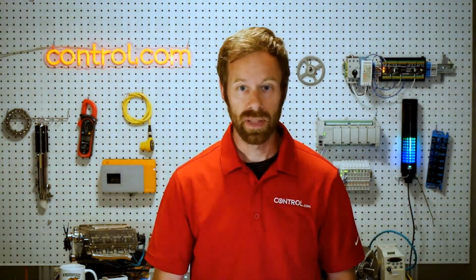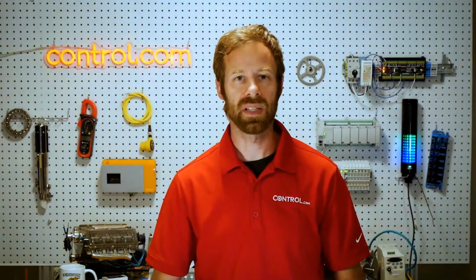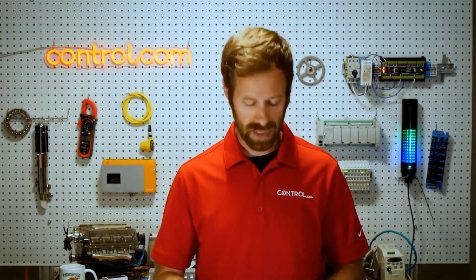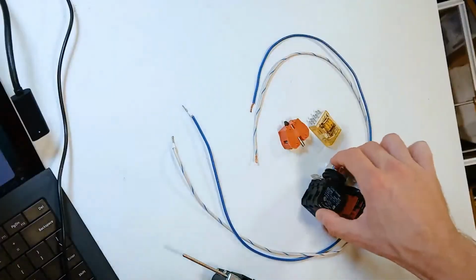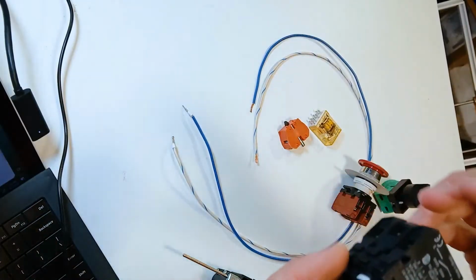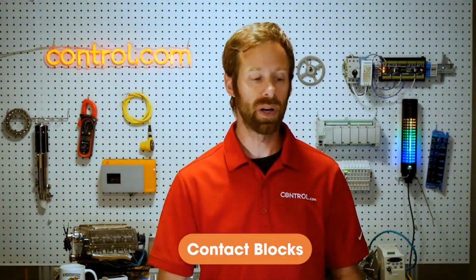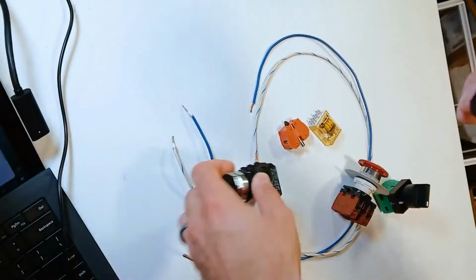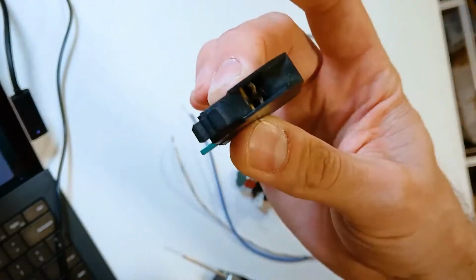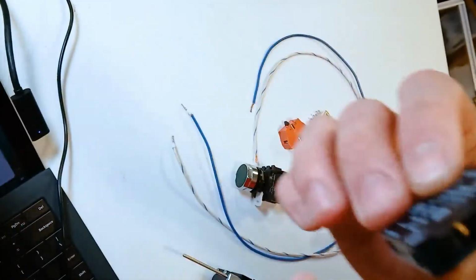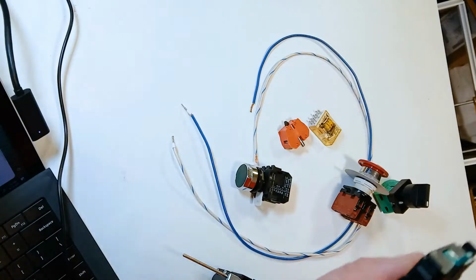But a big question that we'll address with all of these sensors is, how do they work? How do they actually get connected to the control system? Well, mechanical switches, these very simple electromechanical switches, are probably the easiest ones to connect, and they're the most versatile. They have some weaknesses, but we'll get to that in a second. The main way that we connect these is we look at any one of what we call contact blocks, which is the actual part of this switch that's making contact. For all of these switches, I can expose two screw terminals, and these two screw terminals allow electricity to flow in and electricity to flow out.